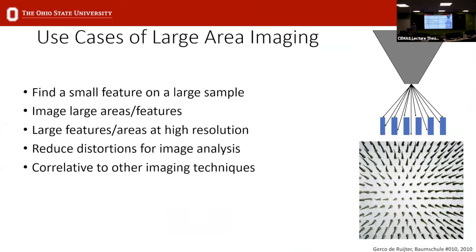The main use cases for large area mapping are: finding a small feature on a large sample — which can cost hundreds of hours of SEM time — so doing a large area map beforehand to navigate back efficiently; imaging large features at high resolution with reduced distortion; and enabling correlation between the electron image, lower resolution maps, and other imaging techniques such as light microscopy, AFM, or TEM for higher resolution work.